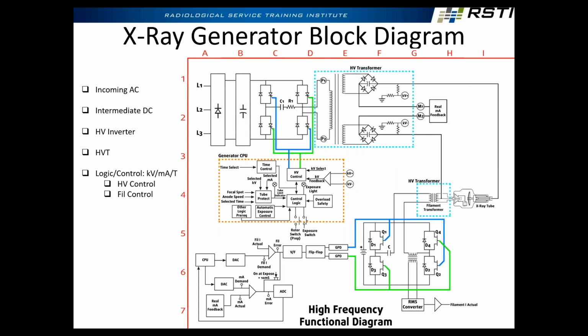Okay, so this is an inverter. I'm taking 480 AC, filtering it and converting it to a fixed DC supply, probably 600 volts to 800 volts DC. Why am I doing this? Because I can control DC better and faster and more efficiently than I can AC. With AC, I have to wait for the wave to pass over zero crossover to turn things on and off, which, when you're talking about milliseconds or microseconds, can have an impact. But with DC, I can turn things on and off really, really fast.